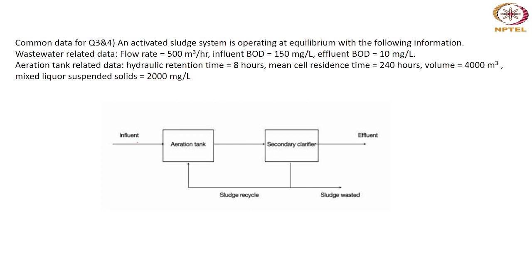Yes, Rujita, I can see your point. Yes, the answer is correct. Is this the formula I use, sir? Flow in meter cube per day into inlet BOD, divided by volume of tank and MLSS in milligram per liter. I use this formula directly and calculate the F/M. Is it right? Yes, right. During examination, I can put this equation to solve the problem.